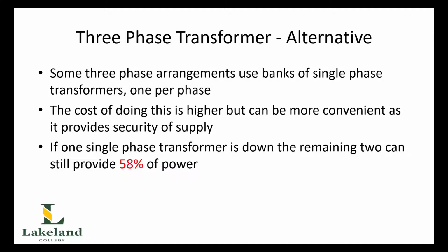And again, this will make more sense after we look at the next chapter, when we look at how you can supply a single-phase load from a three-phase supply. Now, the idea of security of supplies is that for a single-phase transformer, if it goes down, the other two transformers can still provide power. Now, that percentage turns out to be 58% of its total power capacity.